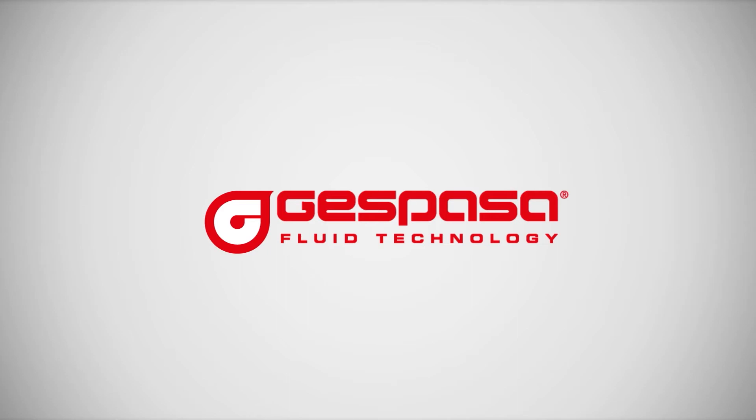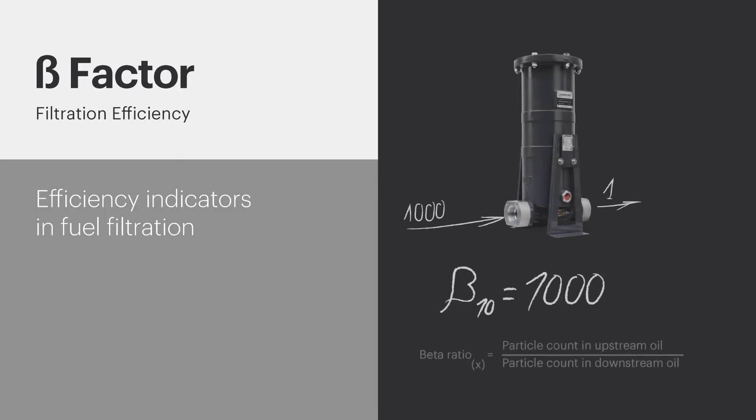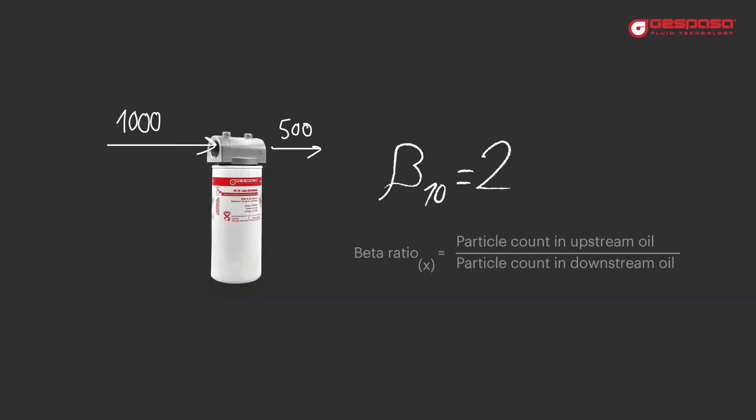What is the beta factor of a filter? The beta factor indicates the efficiency of a filter with respect to the size of the particles. If we say, for example, that a filter is beta 2 at 10 microns, it means that the filter lets through one out of every two particles larger than 10 microns.